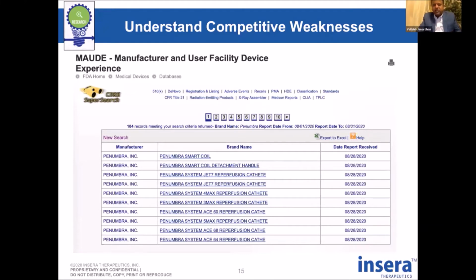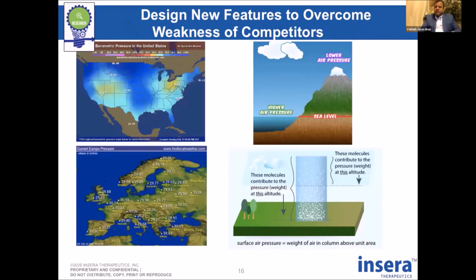We analyzed a lot of this, and one example of a challenge was that analog vacuum aspiration systems are limited by the altitude at which they're used. For example, the maximum suction at sea level at atmospheric pressure is around -29 inches of mercury, which is around -98.2 kilopascals in SI units.